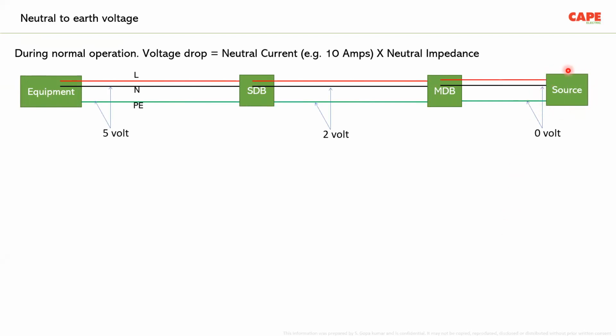On the right side, you have the source, you have the main distribution board, you have the sub distribution board, you have the final equipment. Imagine through the neutral there is a current flow, let's say 10 amperes. As a result of this current flow, if we look at the source, near the source, the neutral and the earth, I'm talking about a TN system, the voltage is 0.